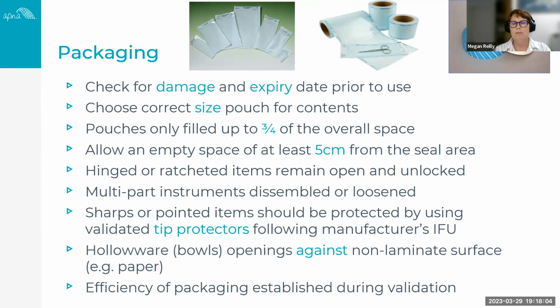And always remember that your packaging needs to be established during the validation of your steriliser on commissioning or recommissioning if that was required, and annually thereafter. So if you change your packaging, say you went from self-seal pouches to rolls and indicator tape, or laminated rolls and a heat sealer, you would need to have your service provider perform validation on that, because you've now changed the process. So that's really important.